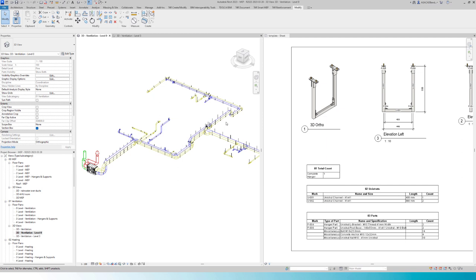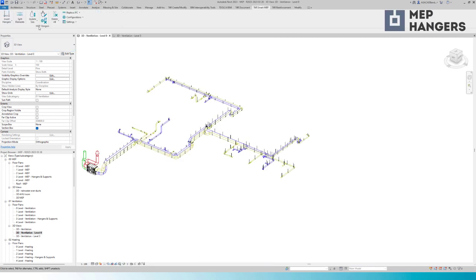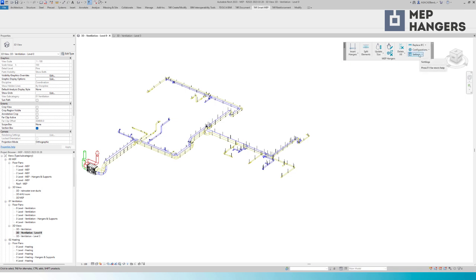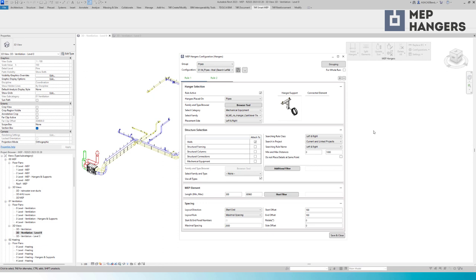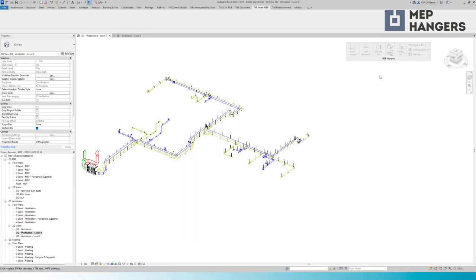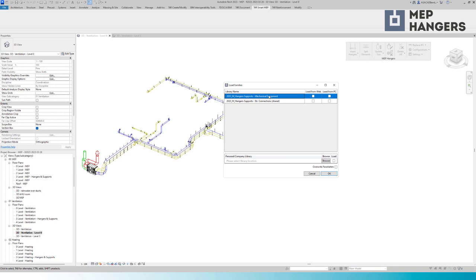I'm in the apartment building project here and this will be our result for today. I already have MEP Hangers installed and I will drag it to the drawing area for quick access. MEP Hangers works on configuration files which are the rules for placing hangers. Configurations are customizable and can be created according to specific needs. Users can have as many configurations or configuration sets as needed. Configurations have the settings for the hangers in use, the structure to attach to, spacing settings, and MEP element filters. We also provide hanger families to work with — you can download them here. Mechanical equipment category families are a bit faster and can be seen in floor plans even when above the cut plane, so I will start with them.